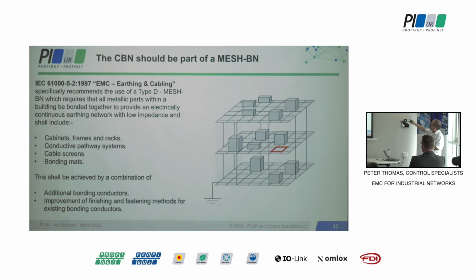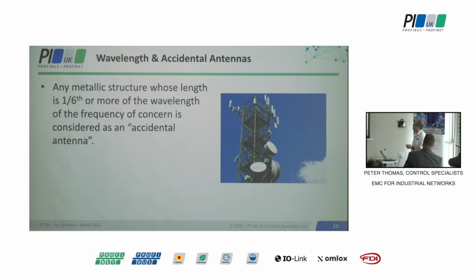This is one of the standards, 61000-5-2, and what it's basically saying is that they would like a brand new installation to move towards this idea of a mesh bonded network, where you've got lots of metalwork in between, such that by definition it's impossible for potentials to exist between them. The dimensions of those meshes depend on the frequency of concern. So if we're at very, very high frequencies, it's going to be small, but maybe more like meter size for the lower frequencies in megahertz, etc.